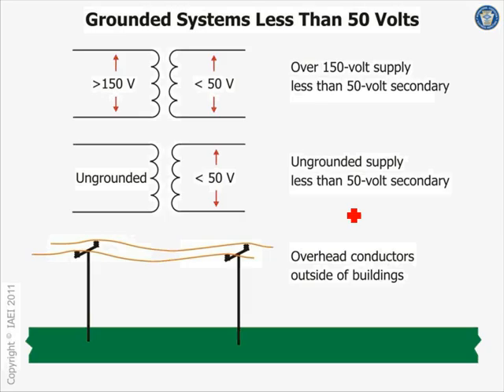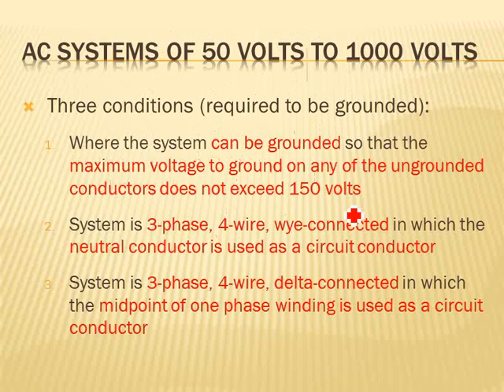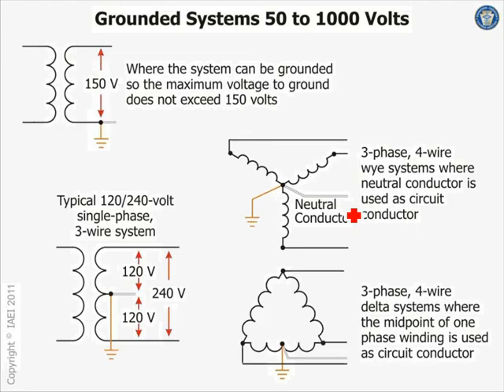If you go outside, you go aerial, you ground. What do you think if you go aerial, like you said? You go aerial here with 24 volt, you ground it likely. You have to ground it. So that's 50 volt or less. Most of us deal with 50 to 1,000 volt, right? With 50 to 1,000 volt, here's your scenario. This is the most common scenario, these two guys. If you have a 3-wire system coming in and you want to utilize the ground, you have to ground the center here to get you 2 voltages.